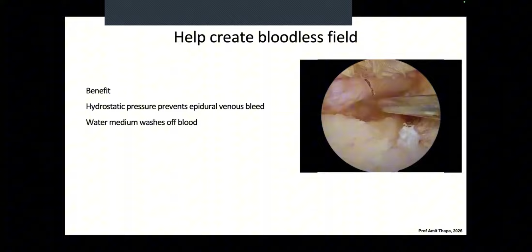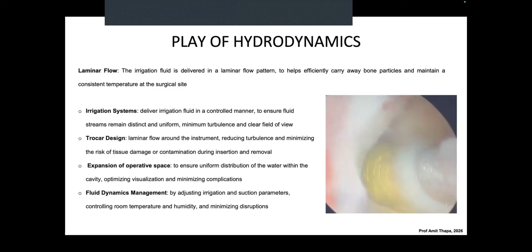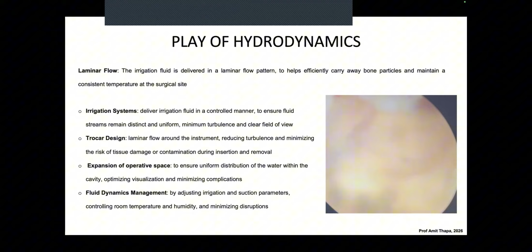Then the other concept is the use of laminar flow. So laminar flow is disrupted whenever you are bringing any instruments inside. So one has to be cognizant about it, because once the laminar flow is disrupted, then the visualization is lost, as the running burrs do cause these types of things. So what one can do is decrease the velocity, or the rotation of the burr, to around 8,000 RPM, and then you can put it in a reverse cutting mode. So this also decreases the chances of pulling tissues inside the burr and makes it safer.